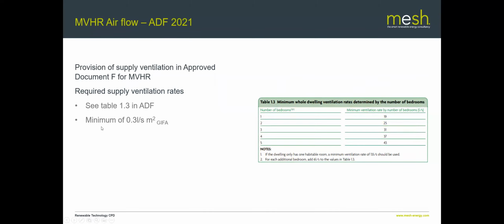So there's a second requirement as well, and this is probably the requirement we end up using most of the time as being what sets the minimum, and that is you must have a minimum of 0.3 litres per second per metre squared of gross internal floor area of the house. So that means you literally add up the floor area of every single room in the house, times that by 0.3, and that gives us our figure. So get my calculator out.